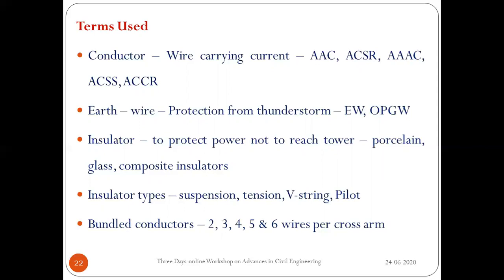Pilot insulators are used at large angle towers on the outer side of a turn to protect the jumper from touching the tower body. Depending on the number of conductors at each cross arm, configurations range from single conductor to double, triple, quad, penta, or hexa (up to six conductors), spaced using spacers.